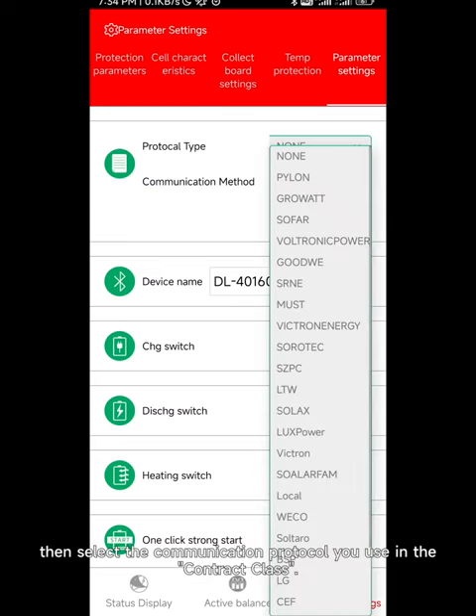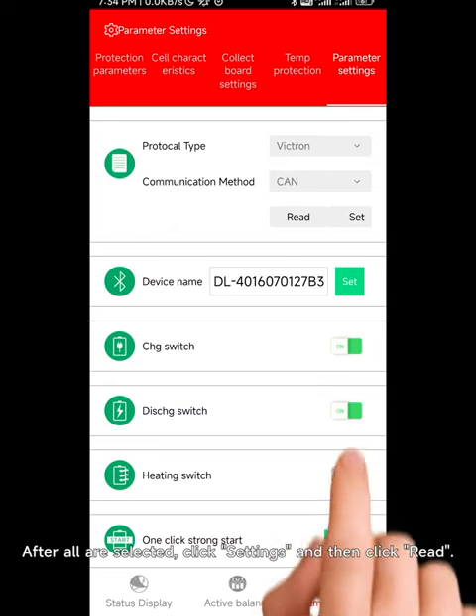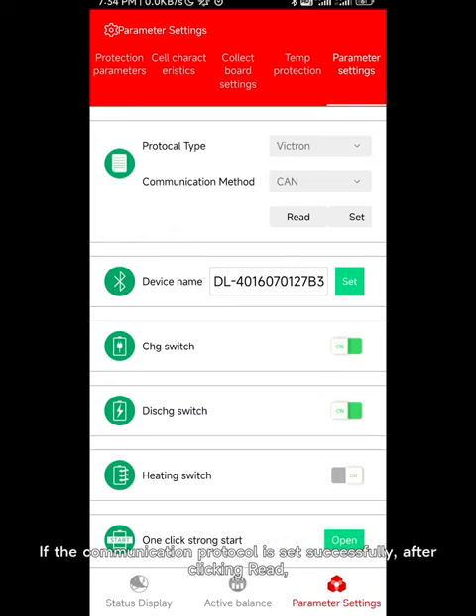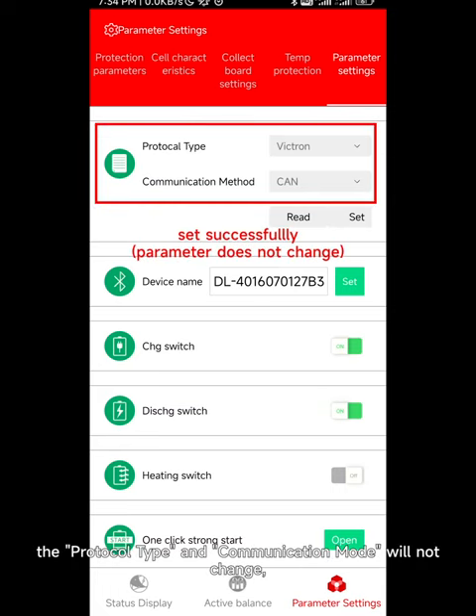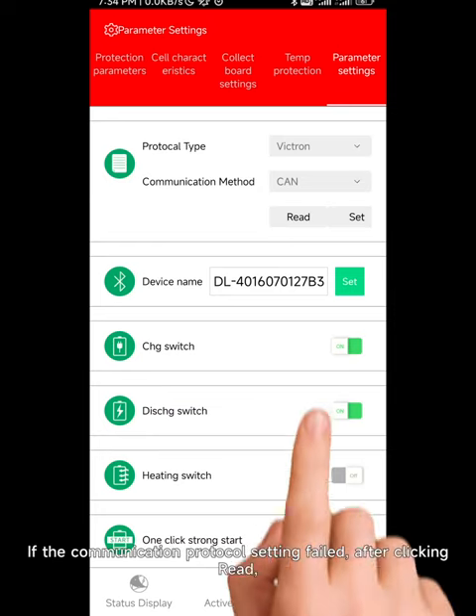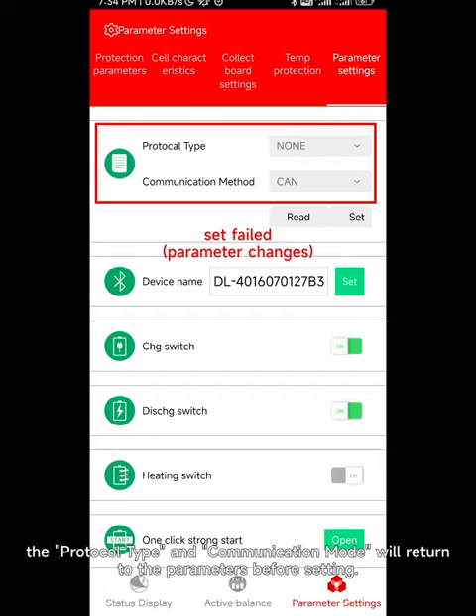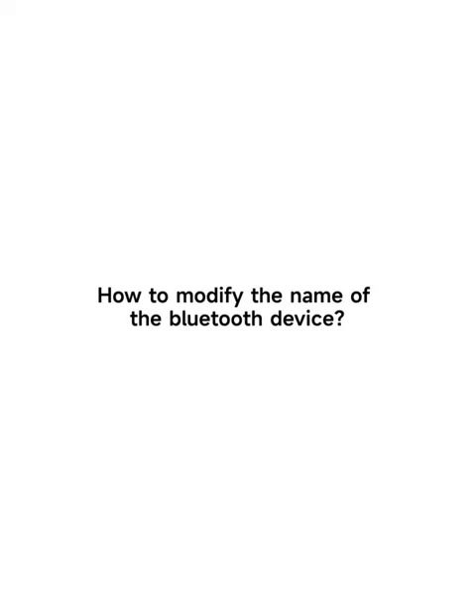In the interface you can see two columns: protocol and communication method. First select CAN or RS485 as the communication method, then select the communication protocol you use. After all are selected, click settings and then click read. If the communication protocol is set successfully, the protocol type and communication mode will not change and will be uploaded to the host computer. If the setting fails, they will return to the parameters before setting.